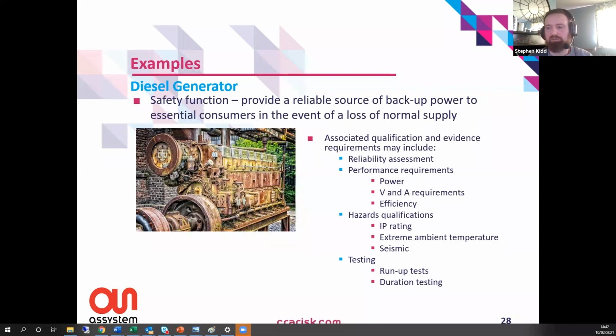And then testing. So the safety case will also have claims on how quickly the power can be provided. So you might have to do run-up tests to demonstrate they can get to steady state running within a specified time. And duration testing, like I said, we'll be looking to provide power for extended durations. We may have to demonstrate that through testing as well.